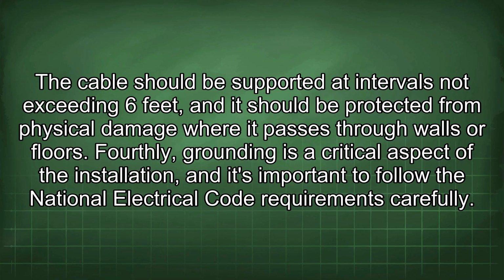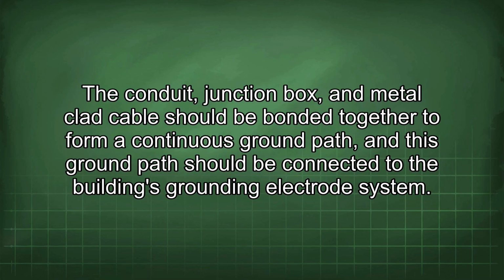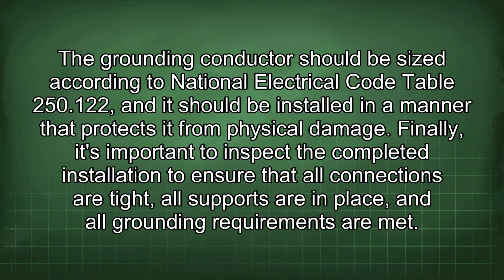Fourthly, grounding is a critical aspect of the installation, and it's important to follow the National Electrical Code requirements carefully. The conduit, junction box, and metal-clad cable should be bonded together to form a continuous ground path, and this ground path should be connected to the building's grounding electrode system. The grounding conductor should be sized according to National Electrical Code Table 250.122, and it should be installed in a manner that protects it from physical damage.